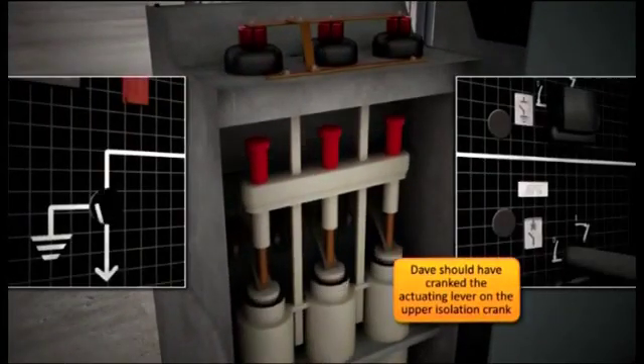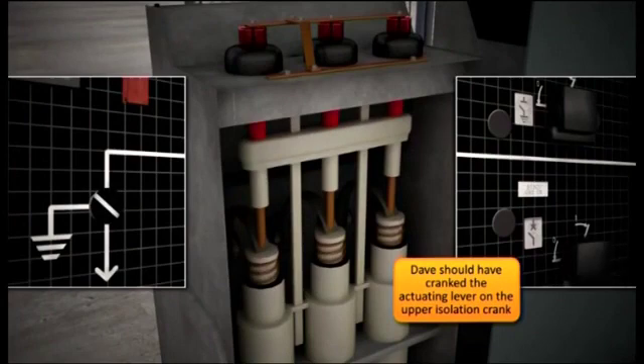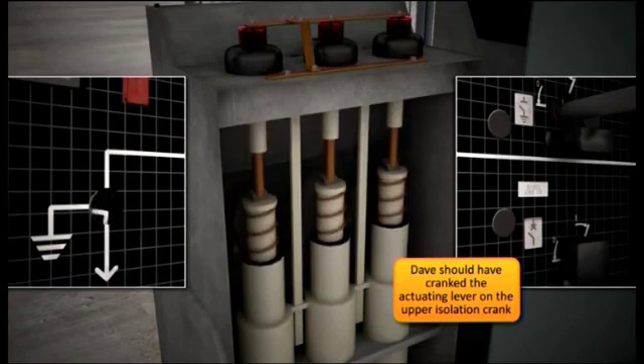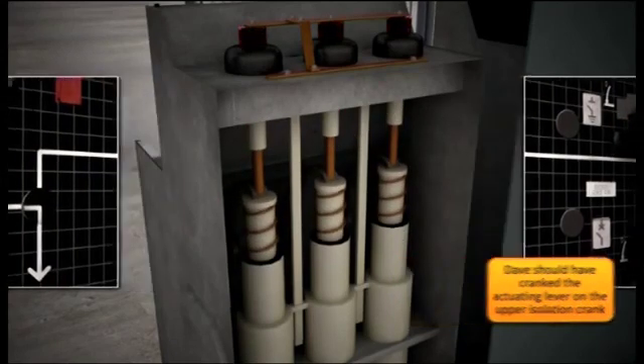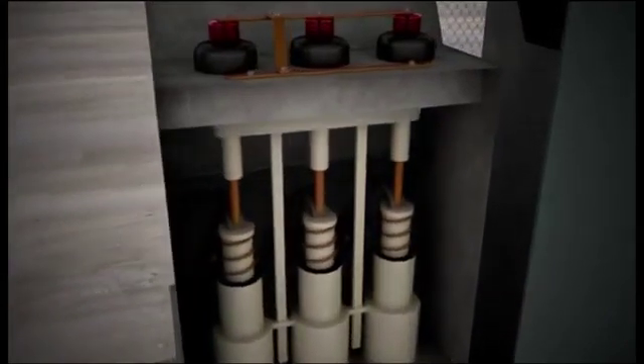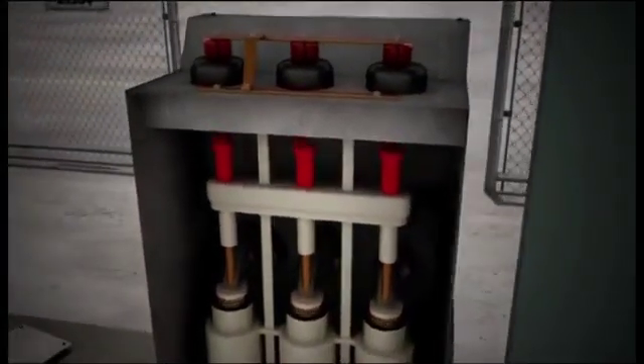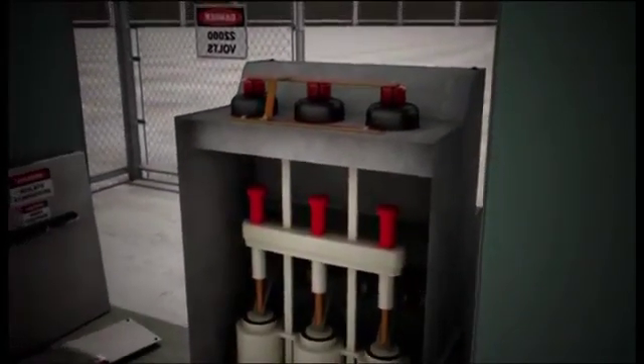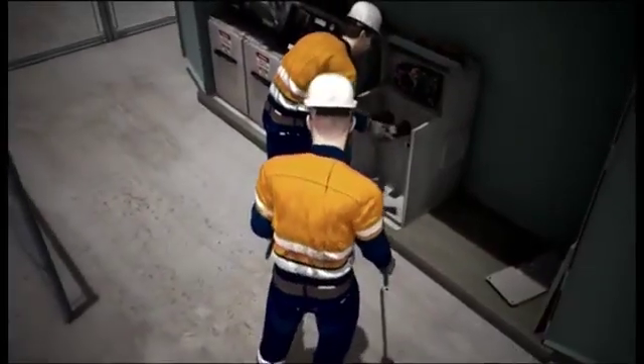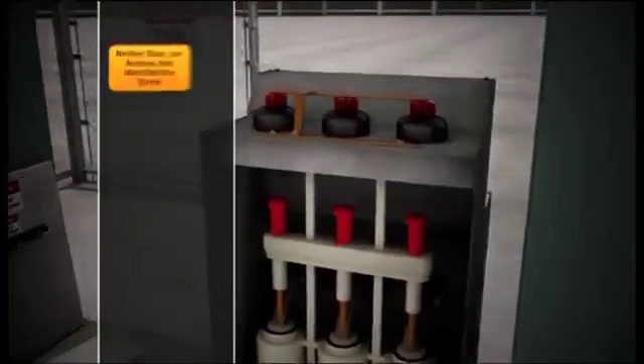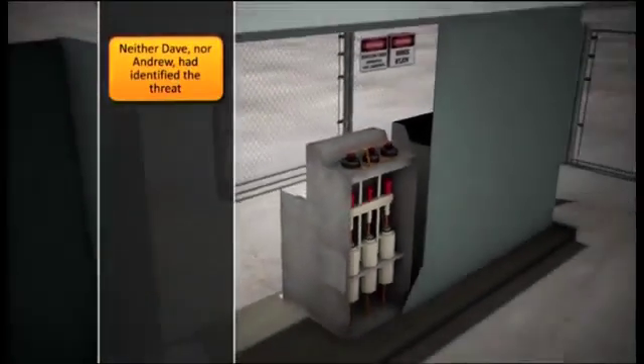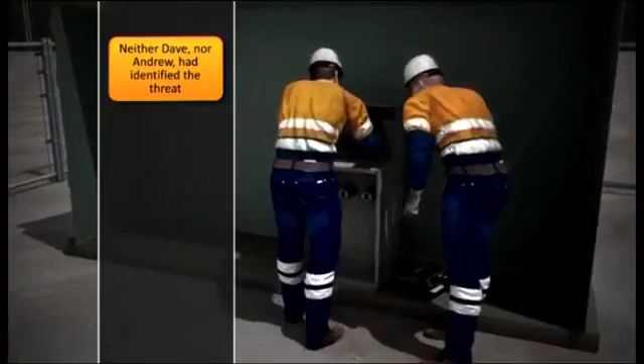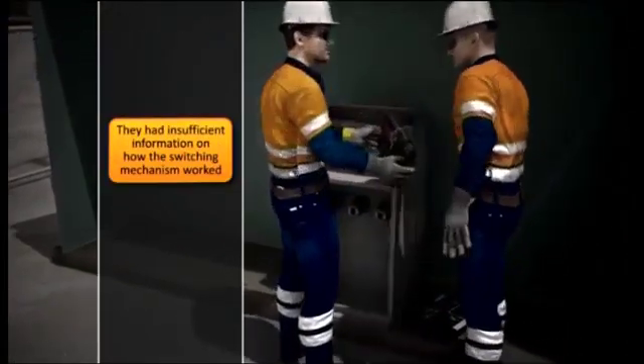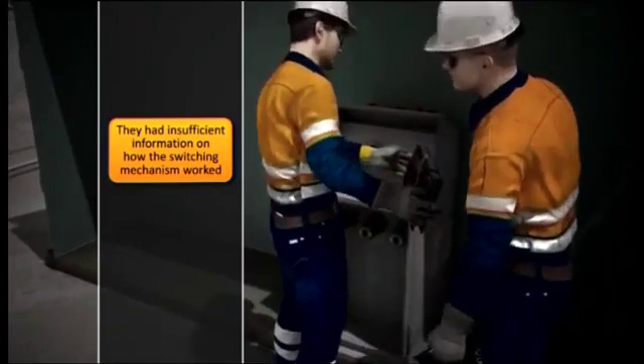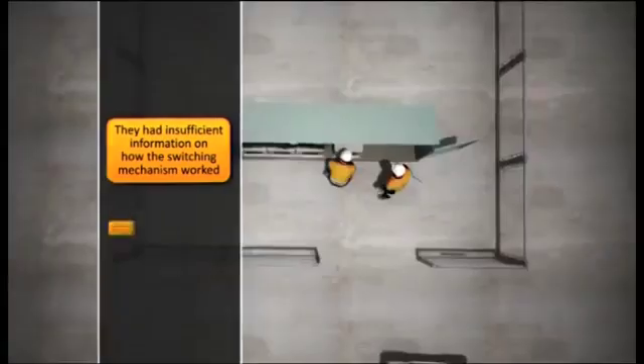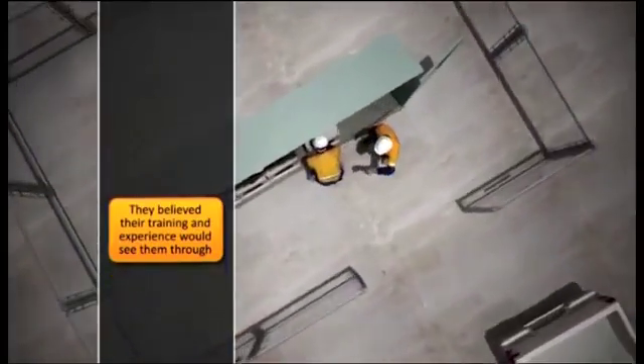If Dave had also worked the actuating lever on the upper isolation crank, the train would have been moved all the way up the tracks and into the earth spouts. Later testing proved that this would not have held the train in place when the switching mechanism was removed. However, it would have dissipated the residual voltages found in the spools during the test for dead. In either case, neither Dave nor Andrew had identified the threat that removing the switching mechanism from the control shaft actually posed. They had insufficient information on how the mechanism worked and how to remove the switch safely. They believed their training and experience would see them through.